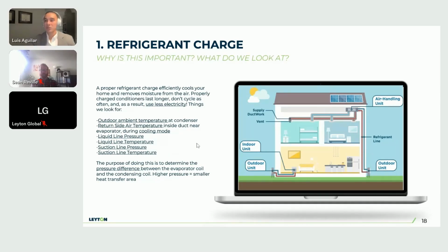Typically for medium temperature systems, like the ones that we see in homes, we're going to see anywhere from 50 to 220 psi pressure difference. It's going to vary depending on the manufacturer, which is why we have to refer to it in the design report, as I stated before. In this case, using the design report, we're going to compare it, and we're going to make sure that the pressure difference is ideal, and that there's not too much subcooling and too much superheating. And if there is, then that could suggest that the refrigerant charge is not where it's supposed to be, and we're going to have to add some refrigerant, or there could be a leak additionally.